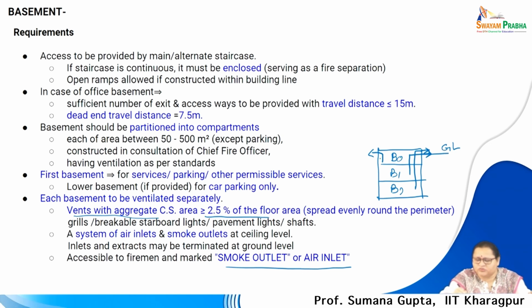There can be air throws from inside into each of these levels, which is the fresh air inlet. Now, these are not habitable spaces. In the upper basement only the services can be put in, but the lower two are only for parking. So usually no human beings are expected other than the drivers for the in and out. It is mandated that all service related requirements should be in the upper basement.